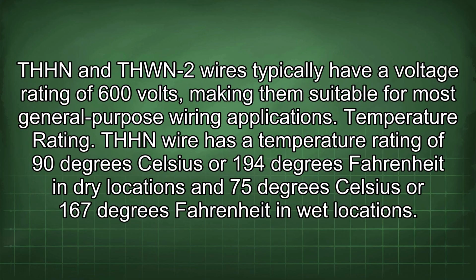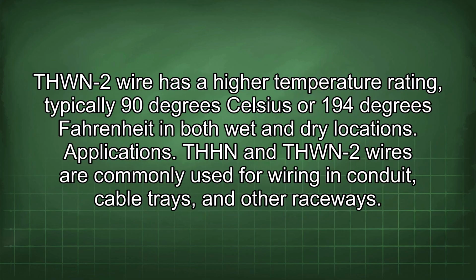Voltage rating. THHN and THWN-2 wires typically have a voltage rating of 600 volts, making them suitable for most general-purpose wiring applications. Temperature rating. THHN wire has a temperature rating of 90 degrees Celsius or 194 degrees Fahrenheit in dry locations and 75 degrees Celsius or 167 degrees Fahrenheit in wet locations. THWN-2 wire has a higher temperature rating, typically 90 degrees Celsius or 194 degrees Fahrenheit in both wet and dry locations.